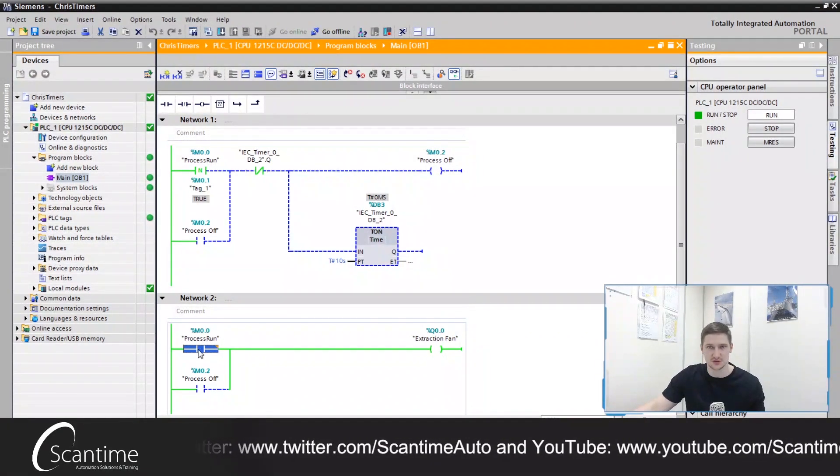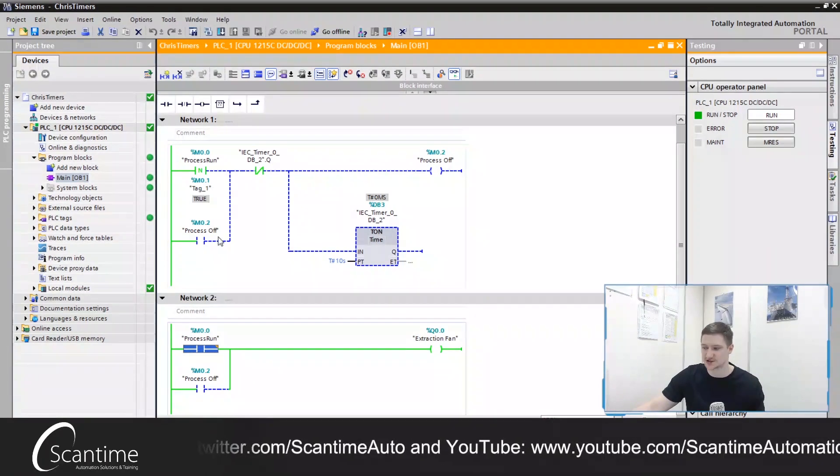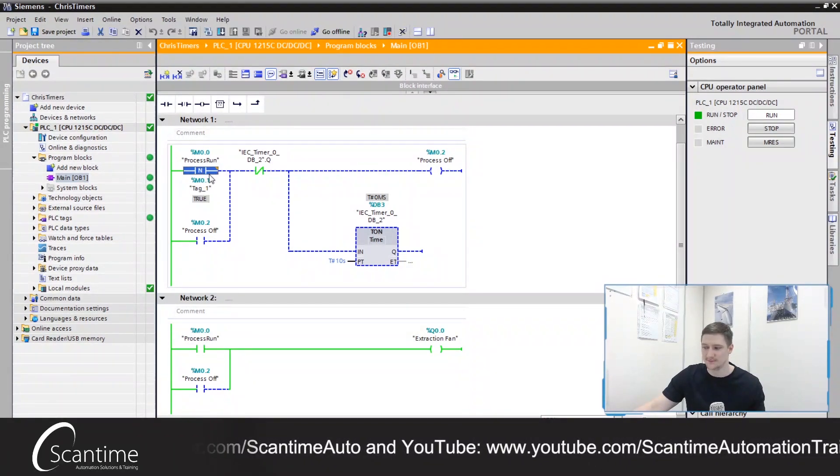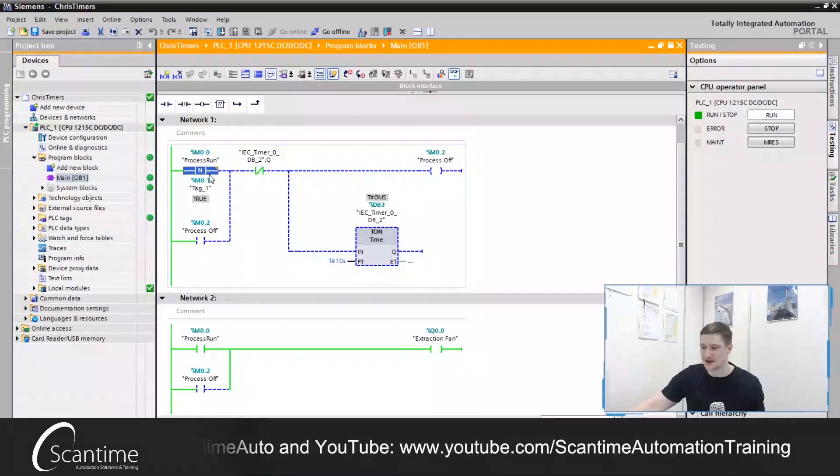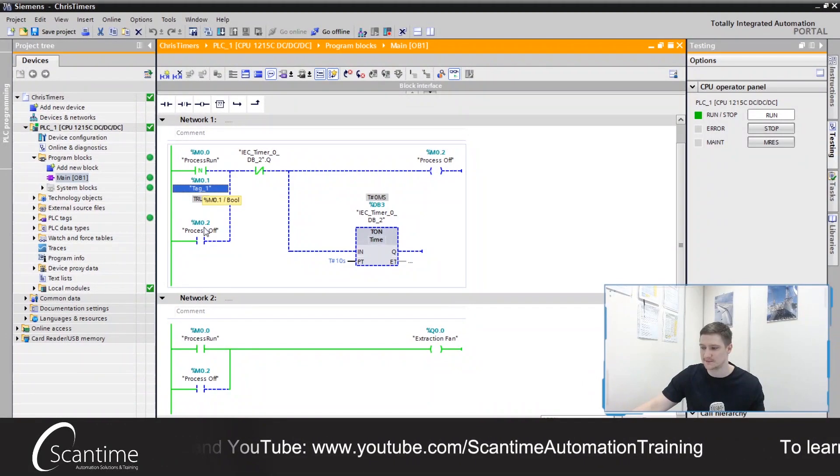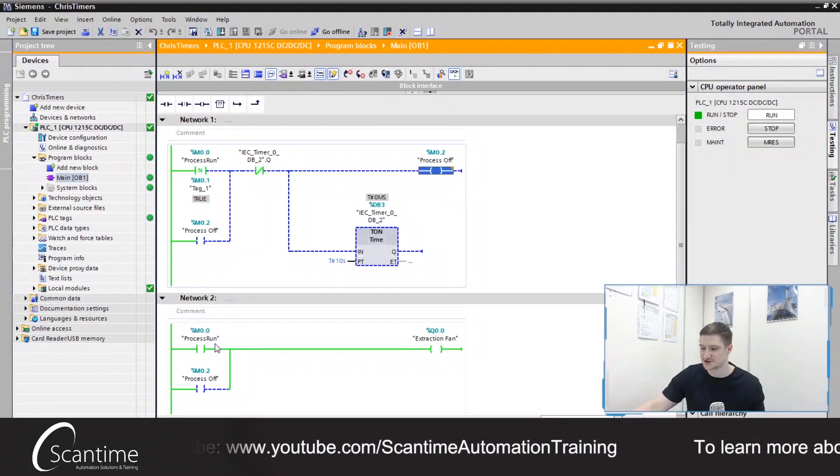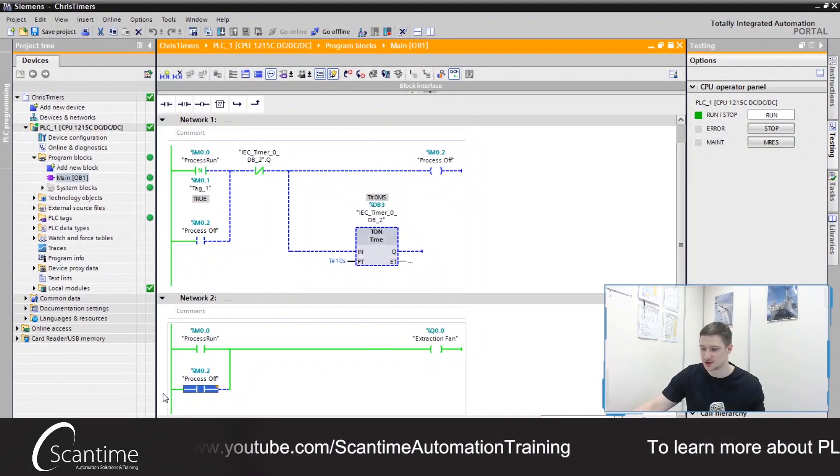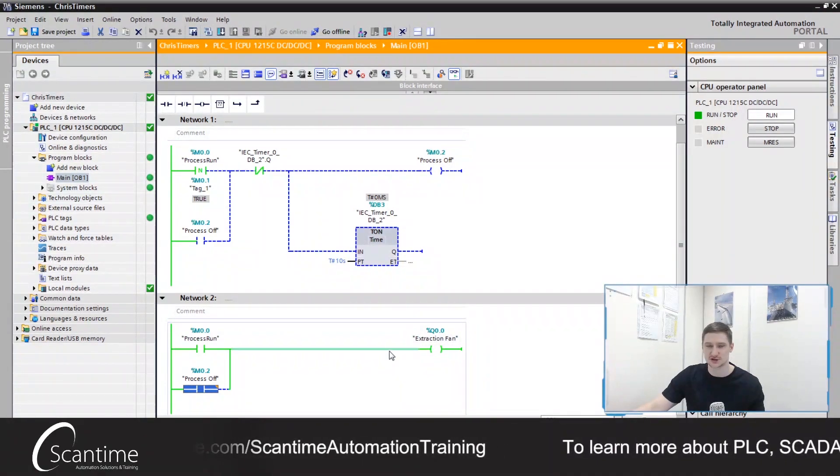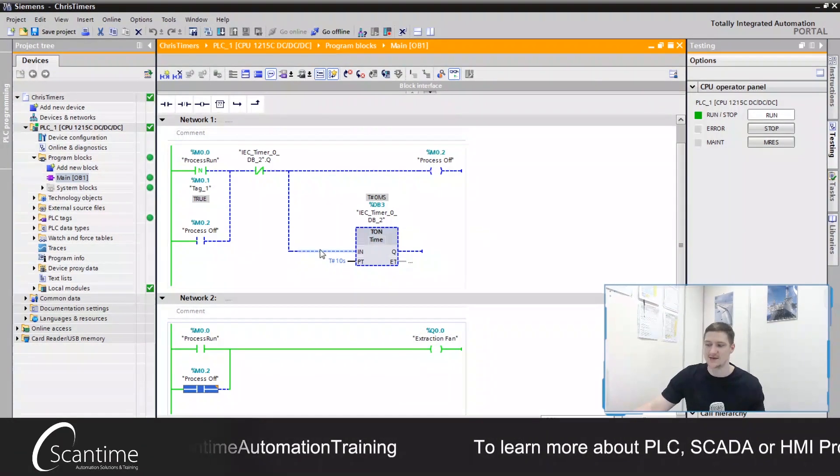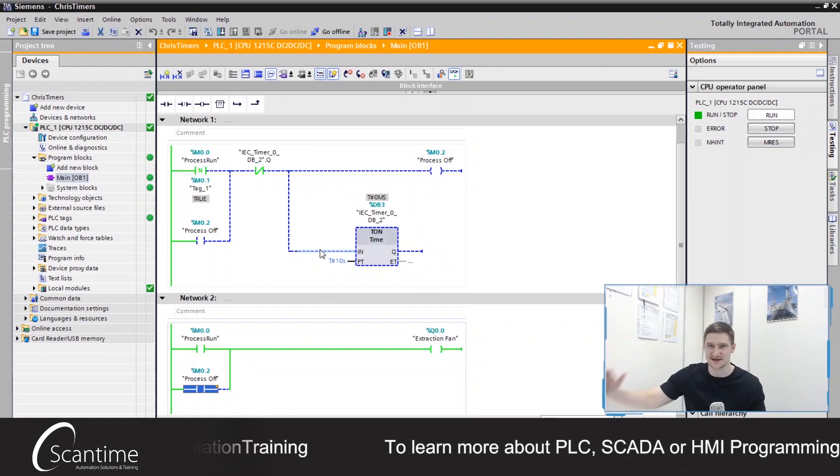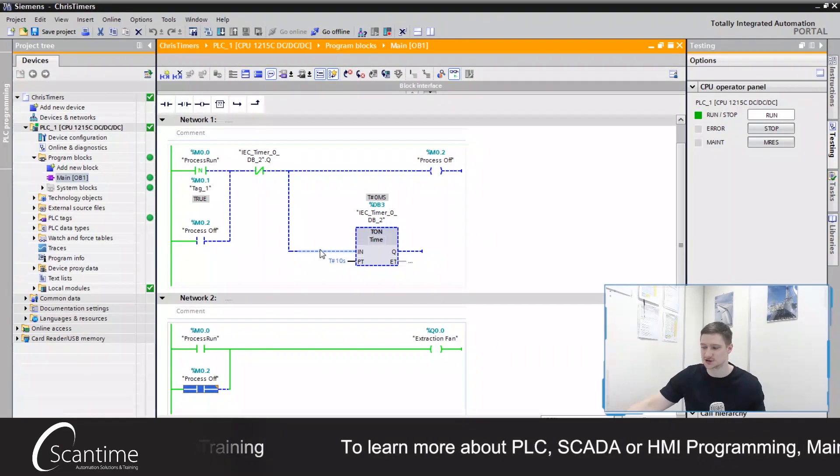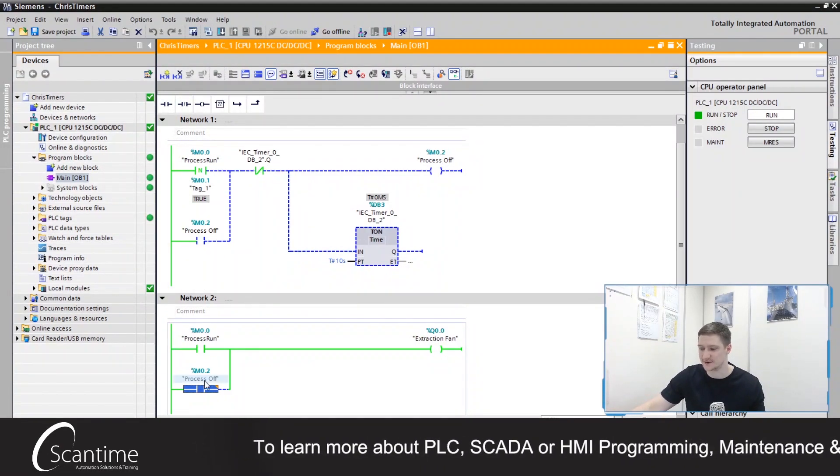So when I unlatch or reset our process run, it'll detect the negative falling edge via the storage bit over here. And it will latch on our process off, which will continue holding the extraction fan on. And then it'll run this timer. After 10 seconds, everything will turn off, including our extraction fan.